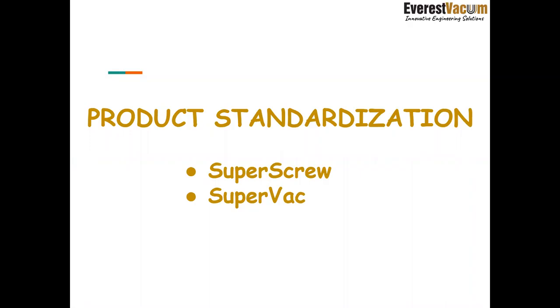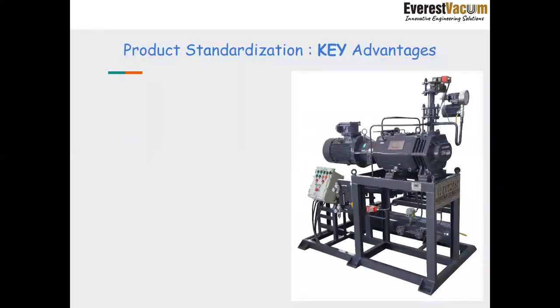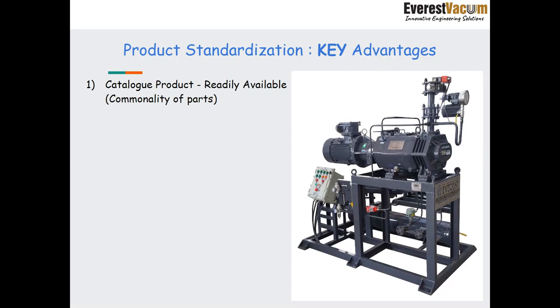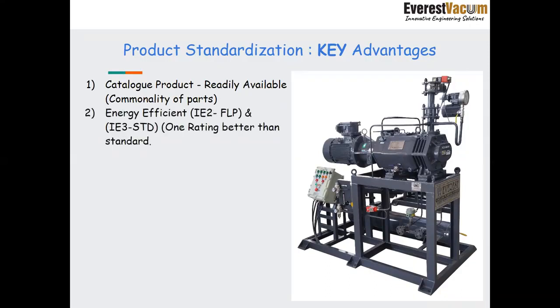Another activity that Everest has come up with is that we have standardized our products in terms of systems as well. Super screws are the dry screw vacuum pumps having various add-on modules, like I have mentioned in the last slides. And SuperVac is a combination of a dry screw vacuum pump and the booster. So we have standardized various products, and the key advantages are that it has become a catalog product. It is readily available. There is commonality of parts across the various modules. Certain accessories are common throughout the standardized models. And in terms of energy efficiency, we have standardized by default IE2 motors for flame-proof and IE3 in standard. So this is one rating better than what we used to supply in the standard ratings.